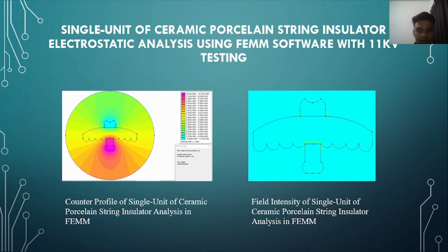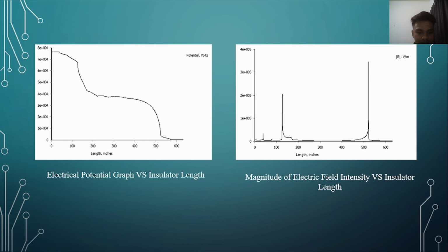So this is the intensity of the single unit ceramic porcelain string insulator analysis in FEMM. The field intensity is concentrated in the center of the design between the insulator pin and the porcelain. Next, the electrical potential graph along the insulator line, and the result graph for the magnitude of electric field intensity versus insulator line. The single insulator design is not problematic since there is only a little electric field present at the insulator.